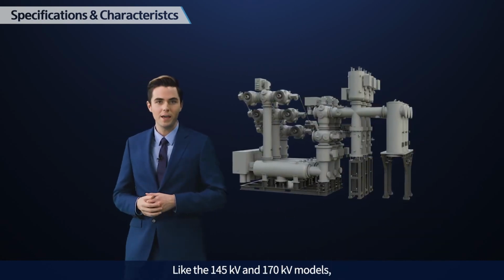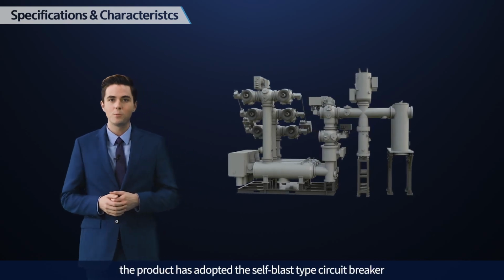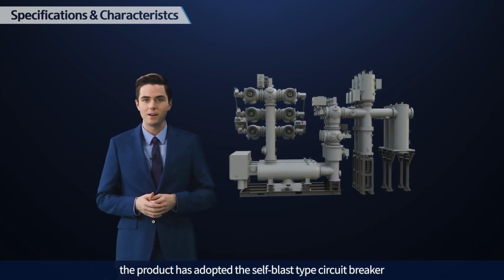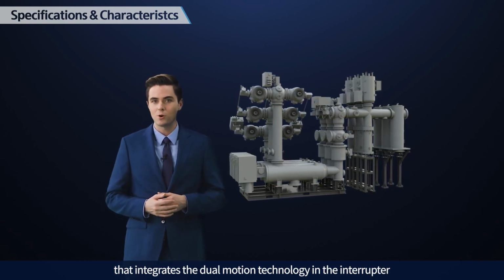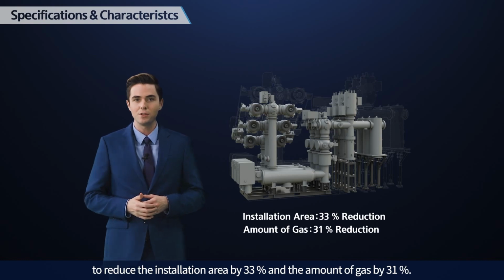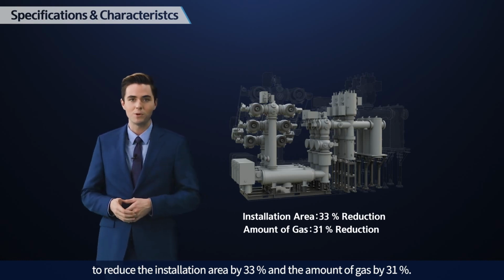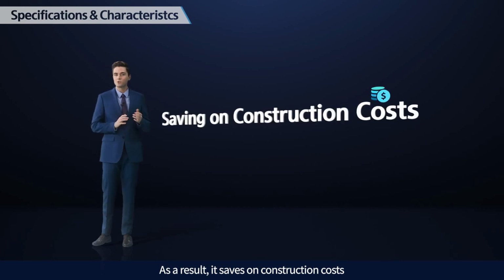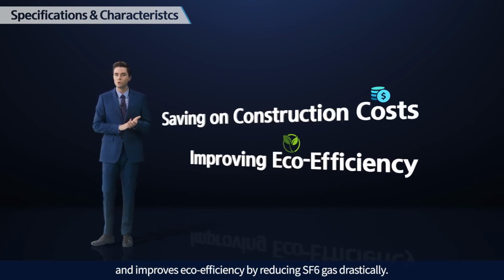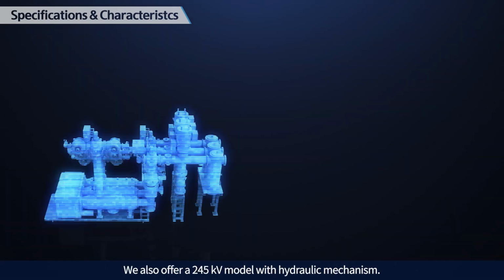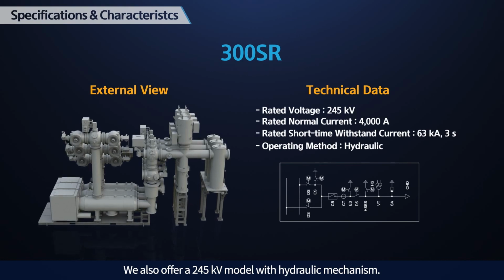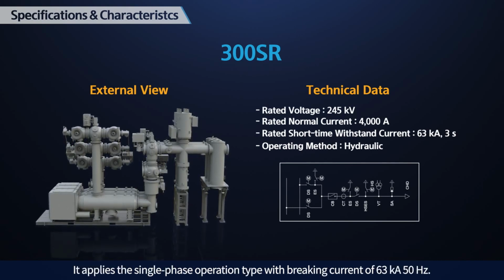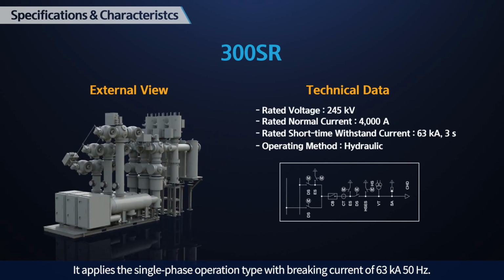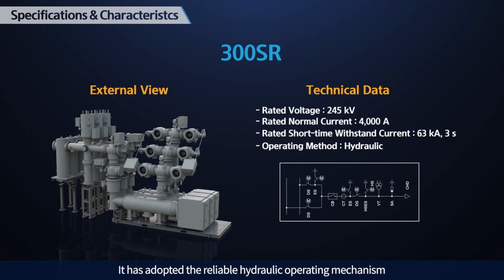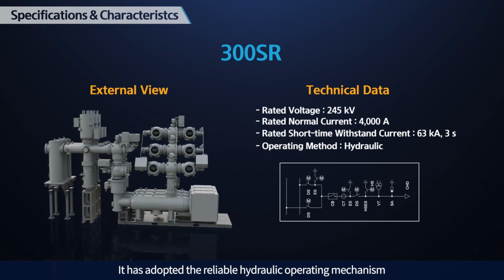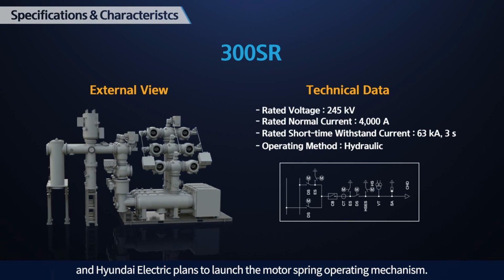Like the 145 kV and 170 kV models, the product has adopted the self-blast type circuit breaker that integrates the dual motion technology in the interrupter to reduce the installation area by 33% and the amount of gas by 31%. As a result, it saves on construction costs and improves eco-efficiency by reducing SF6 gas drastically. We also offer a 245 kV model with hydraulic mechanism. It applies the single-phase operation type with breaking current of 63 kA, 50 Hz. It has adopted the reliable hydraulic operating mechanism, and Hyundai Electric plans to launch the motor spring operating mechanism.